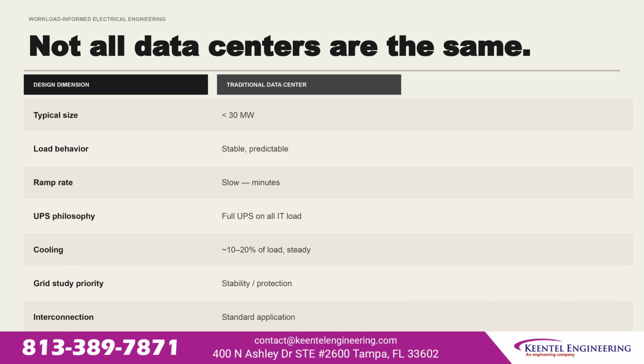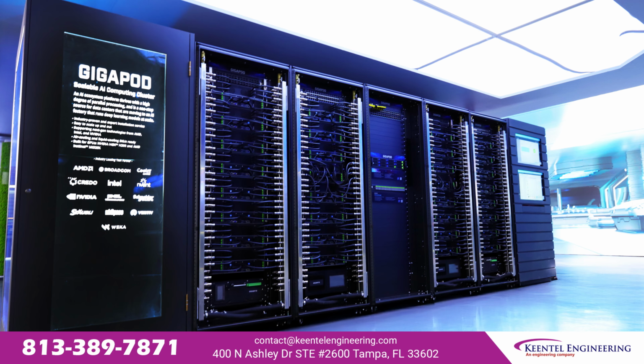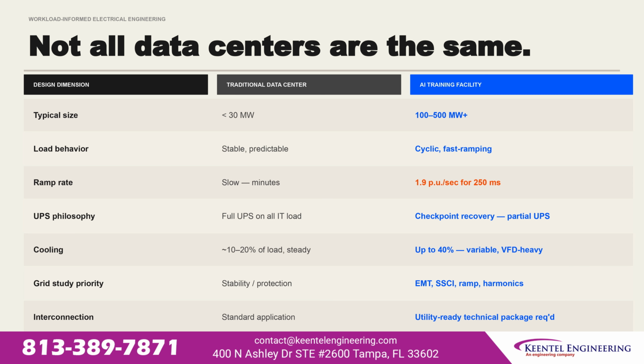Not all data centers are the same, and designing them with the same template is an engineering error. Traditional data centers: typically under 30 megawatts, stable predictable load, slow ramp rates in minutes, full UPS on all IT load, steady cooling at 10 to 20% of total load, and a standard interconnection application. AI training facilities: 100 to 500 megawatts and growing, cyclic fast-ramping load, ramp rates of 1.9 per unit per second for 250 milliseconds, checkpoint recovery with partial UPS, cooling up to 40% of total load with VFD-heavy variability. EMT, SSCI, ramp, and harmonic studies are required. A utility-ready technical package is mandatory. The electrical design must follow the workload, not a generic template.